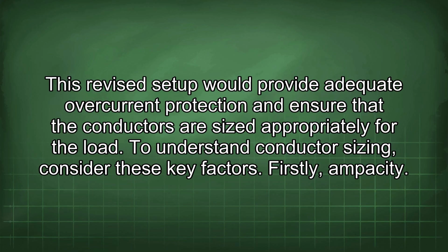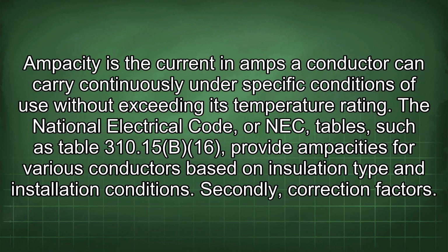To understand conductor sizing, consider these key factors. Firstly, ampacity. Ampacity is the current in amps a conductor can carry continuously under specific conditions of use without exceeding its temperature rating. The National Electrical Code, or NEC, tables such as Table 310.15(B)(16) provide ampacities for various conductors based on insulation type and installation conditions.